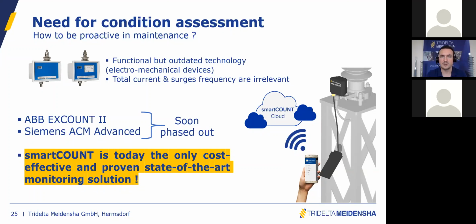I would say it also depends on the countries. These days, we see a lot of utilities switching from porcelain to silicone, and with the existing portfolio, you can easily fulfill requirements with a cage design up to 500 kV system voltage. But then you will see in some places, for example in Germany, Quebec or France, you are not able to use those cage designs because you have specific mechanical requirements. So it's all about mechanical requirements.